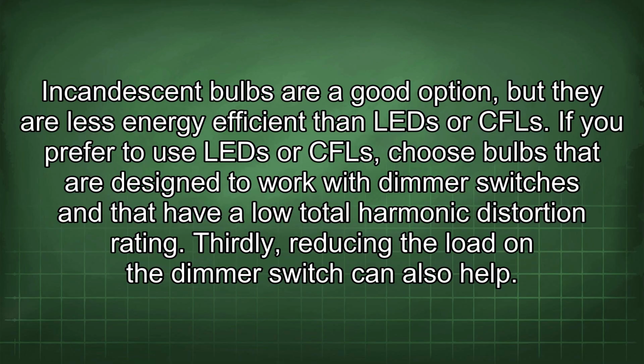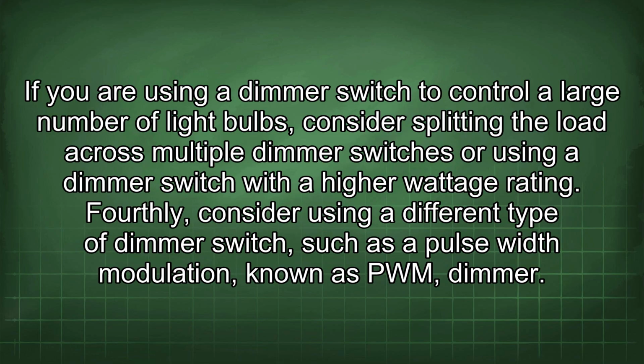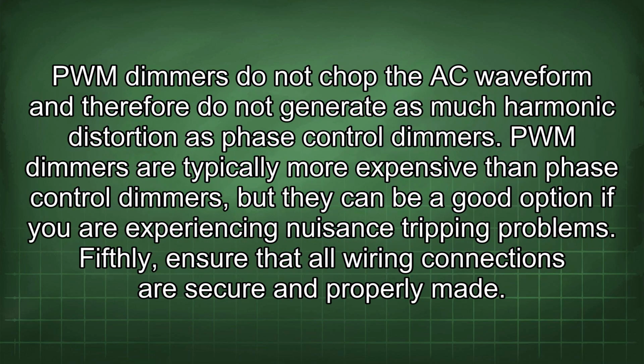Thirdly, reducing the load on the dimmer switch can also help. If you are using a dimmer switch to control a large number of light bulbs, consider splitting the load across multiple dimmer switches or using a dimmer switch with a higher wattage rating. Fourthly, consider using a different type of dimmer switch, such as a pulse width modulation, known as PWM, dimmer. PWM dimmers do not chop the AC waveform and therefore do not generate as much harmonic distortion as phase control dimmers. PWM dimmers are typically more expensive than phase control dimmers, but they can be a good option if you are experiencing nuisance tripping problems.